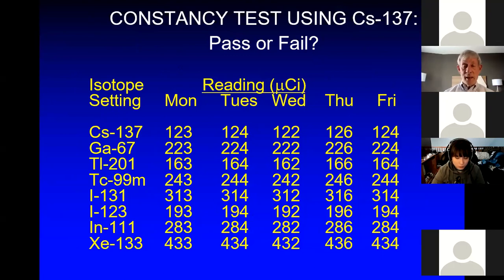But is this a pass or a fail? You just want to read across and look at the constancy of the numbers. Pass or a fail? Pass. Totally a pass. Again, a beautiful constancy test. You're lucky to get one that good, but that's what you expect to see. You expect to see the same wrong number.